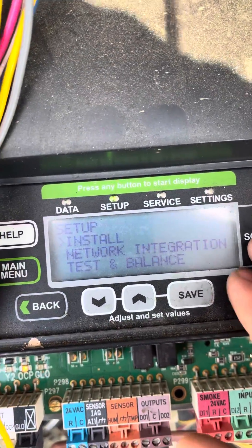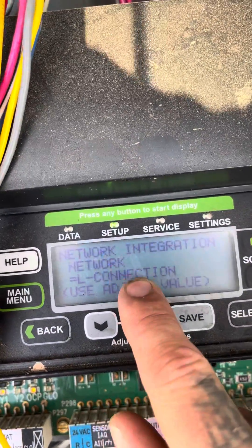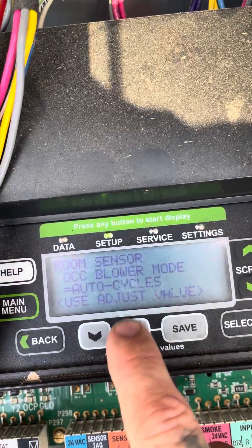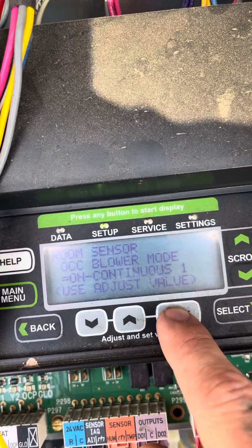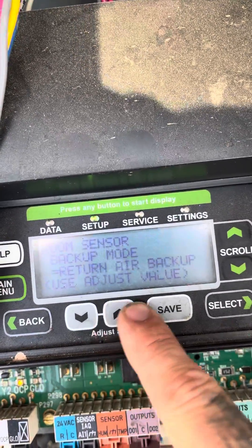Go to Setup, then go to Network Integration. We got L-Connection — we're going to change that to Standalone, hit Save. Blower, we don't want it on Auto Cycle — we're going to go Continuous On, save. Backup mode, we want to run that on Return Air Sensor.